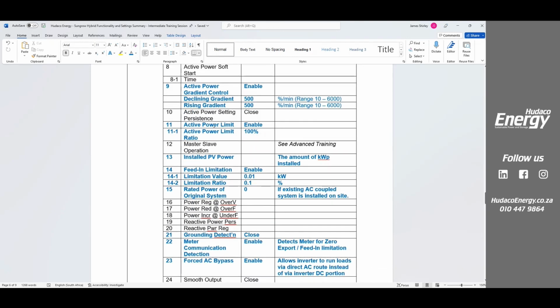This active power limit that we spoke about, we can limit the production from the system to meet a certain level. I've only ever done this once, and again, it was to protect cable sizes. If an installer has installed the wrong cable size, we can manage this, and we would just turn down and say, listen, you're not safe at the moment. You're trying to produce, say, 10 kilowatts, but your cable can only handle 5 kilowatts safely, right? So that's where and how we could limit that.